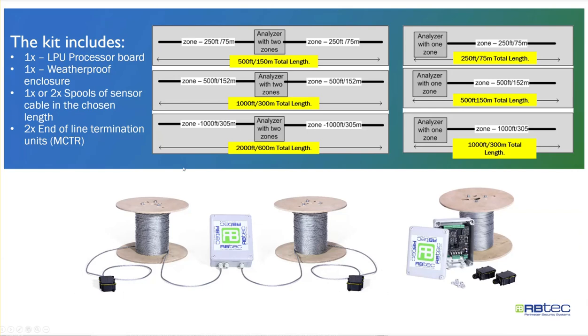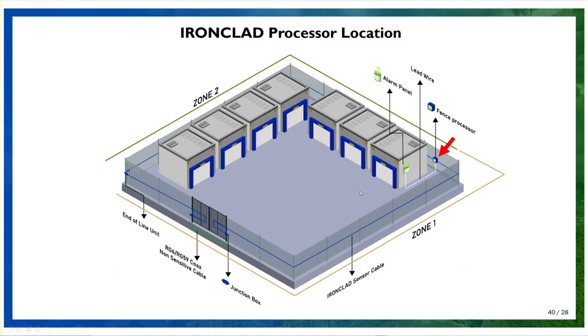Now, when the system is installed on site, you cut the cable to the exact length of the zone, and you terminate it with an end-of-line termination, and that's it. A standard layout of the system is that we're going to have a processor with 2 zones that are wrapping around the site. In this specific site, we might have 3. And each zone is a dead end. It's not a loop. It starts at the processor and just ends in the end-of-line termination. The only location we need power and where we're taking the contact closure relay outputs is where the processor is.